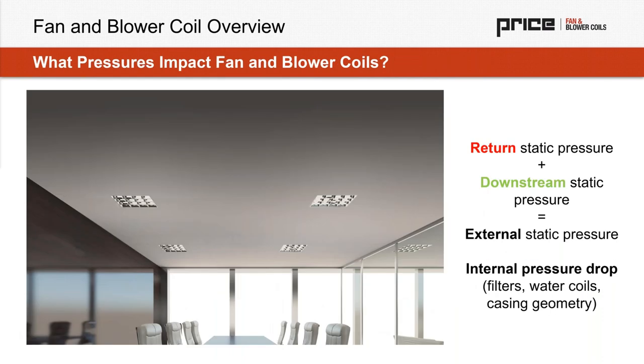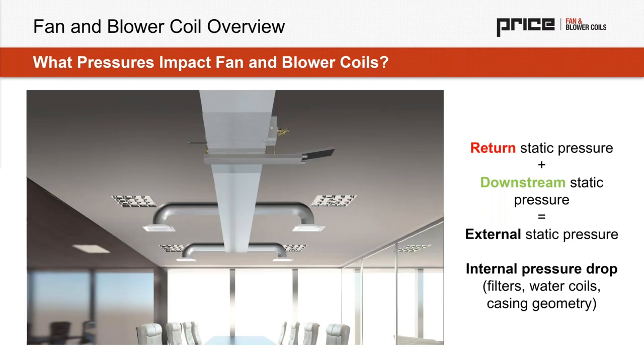When we look at integration to the HVAC system, we also need to be very considerate of the duct system and the way that it impacts and influences fan and blower coil performance. So in this case, we have an office zone, a little conference room, and we could have a quiet, high performance fan coil mounted above the ceiling. And we need to be considerate of the return ductwork and the increase of return static pressure drop as we start to see that duct run grow, or as we start to see velocity increase through that duct run. That is negative pressure because the fan is actually acting as a vacuum, sucking air through that ductwork. And we also have to be considerate of downstream static pressure, so the static pressure drop of downstream duct, duct fittings and diffusers.